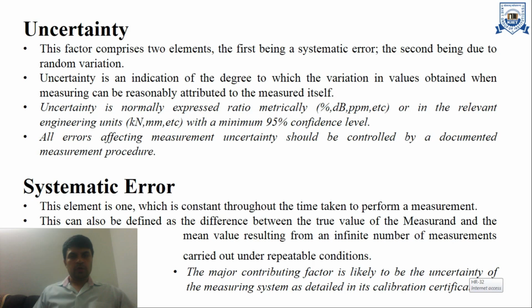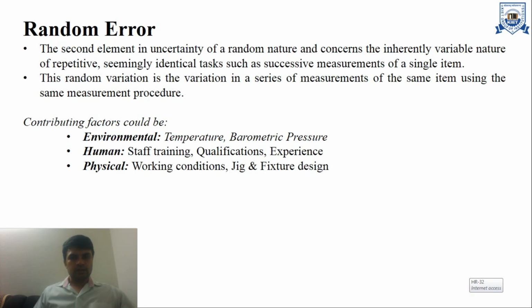Then we have systematic error. This element is one which is constant throughout the time taken to perform a measurement. It can be defined as the difference between the true value of the measurand and the mean value resulting from an infinite number of measurements carried out under repeatable conditions. The major contributing factor is likely to be the uncertainty of the measuring system as detailed in its calibration certificate.